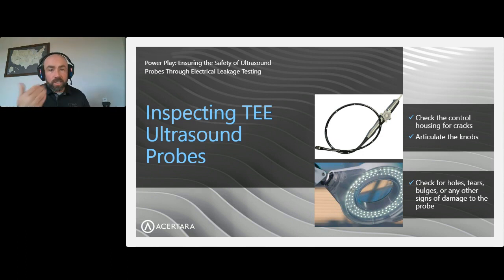On the control housing, you want to check the control housing for cracks. I mentioned earlier you want to articulate the knobs. If you don't start getting a response from the end of the TEE probe as soon as you start turning that knob, those cables will stretch. The actual setting could come loose, and you're going to start to see that manifest, and physicians will complain about that too. So if you can find it ahead of time, you can save some trouble. On all of these things, you're looking for holes, tears, bulges, or even areas that are discolored. You want to pay attention to those, because that can indicate that underlying material is compromised.